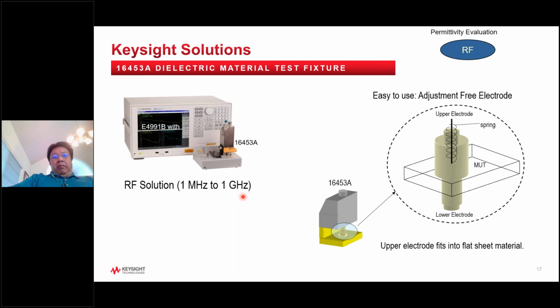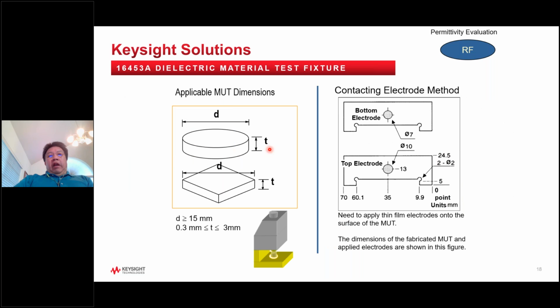The difference between this solution and the previous one is that the frequency is higher, using a different fixture. In this particular case, the fixture has a spring load, so that you don't have an air gap problem. However, if your sample is soft, then it may affect your thickness. One of the parameters of material measurement is that we need to know precisely the thickness of your material, because thickness is used to calculate your permittivity. In this solution, we incorporate a different type of calibration so that it has better accuracy compared to the previous solution. Again, it comes with a couple of different sample electrodes.